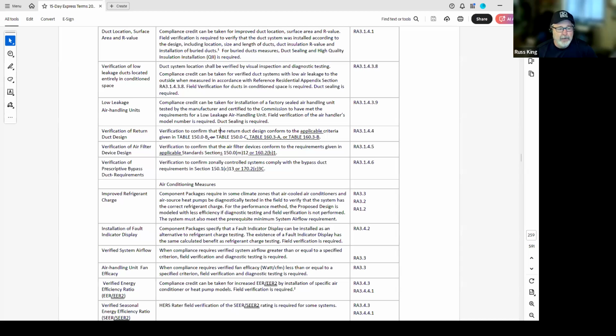Other building departments have just realized it's in the code and are enforcing it, but it's growing. Now, what are the allowed heating and cooling load calculation methods? The code says ASHRAE, which is really going back to the basic math. It also mentions SMACNA, which shouldn't really be in there. If you read the SMACNA duct installation standards, they refer to Manual J. So I don't know why SMACNA is even mentioned, honestly.